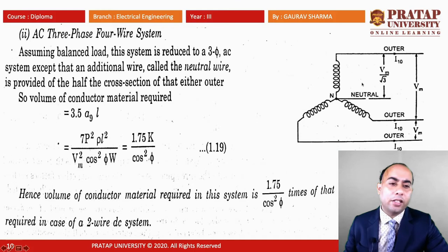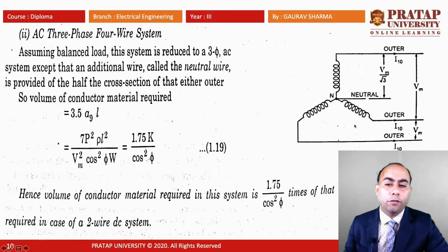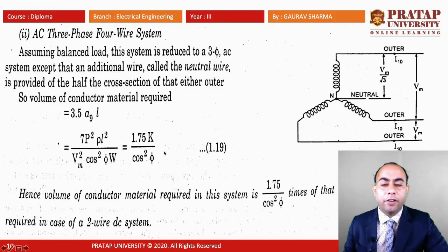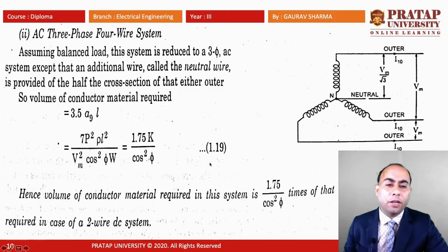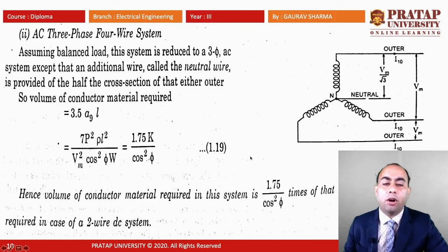For the three phase four wire AC system, there are three outer conductors and a neutral wire whose cross section is just half of the outer conductor. The volume of conductor material required is 3.5·A9·L = 1.75K/cos²φ. Hence the volume required in the three phase four wire system is 1.75/cos²φ times that required in the DC two wire system.